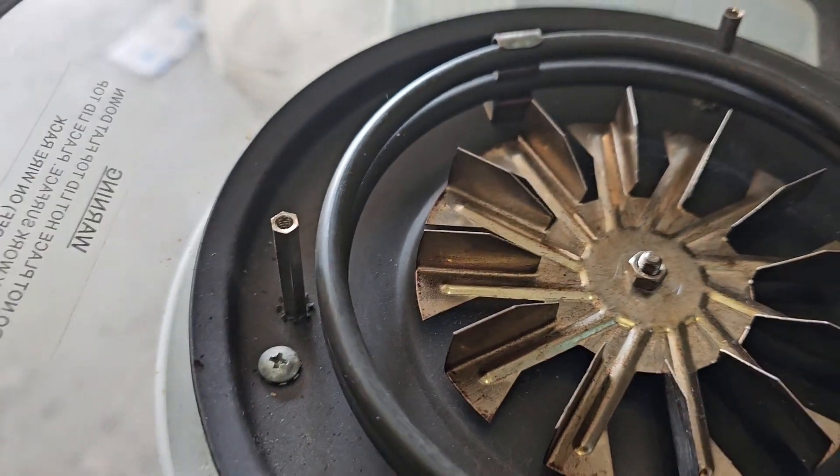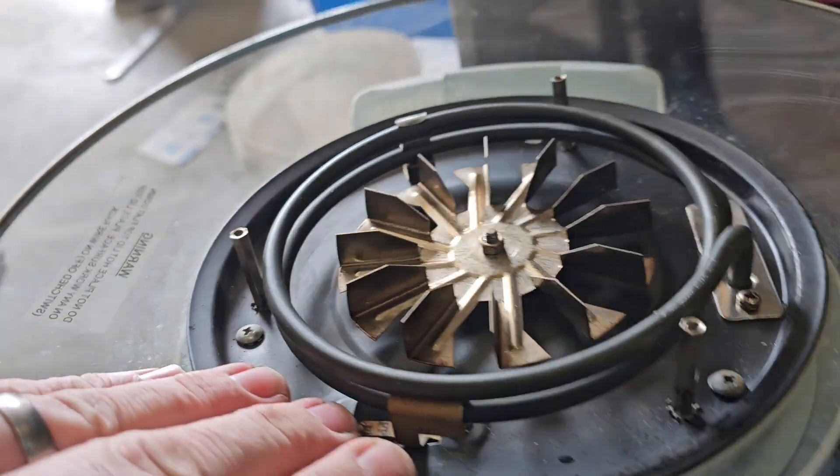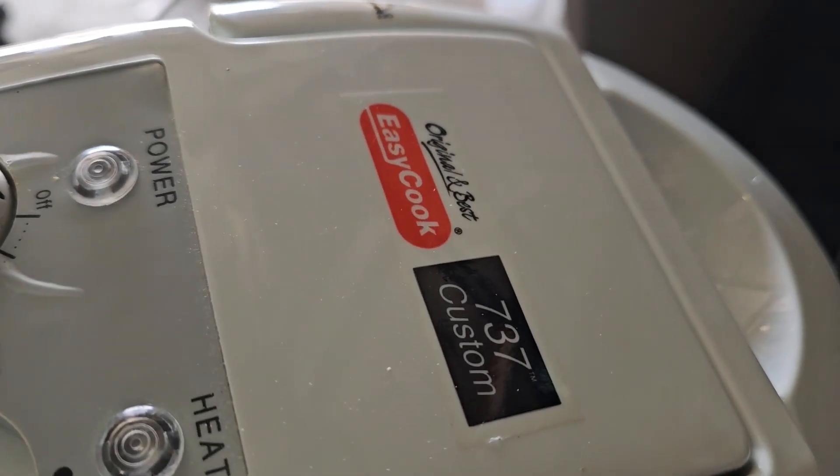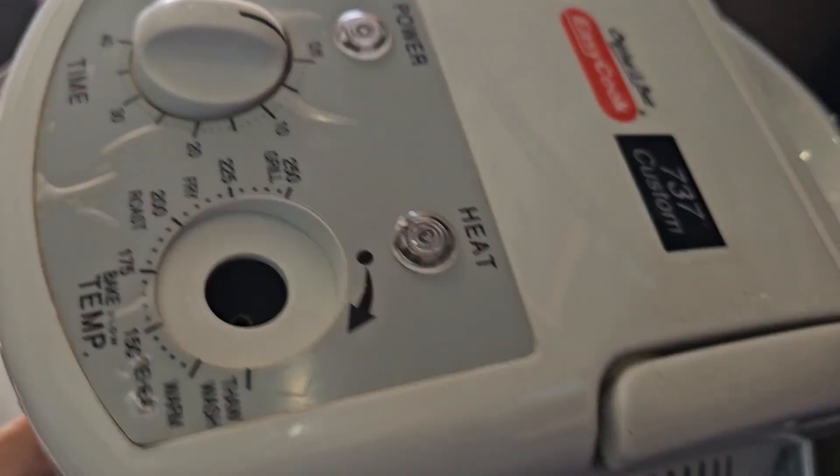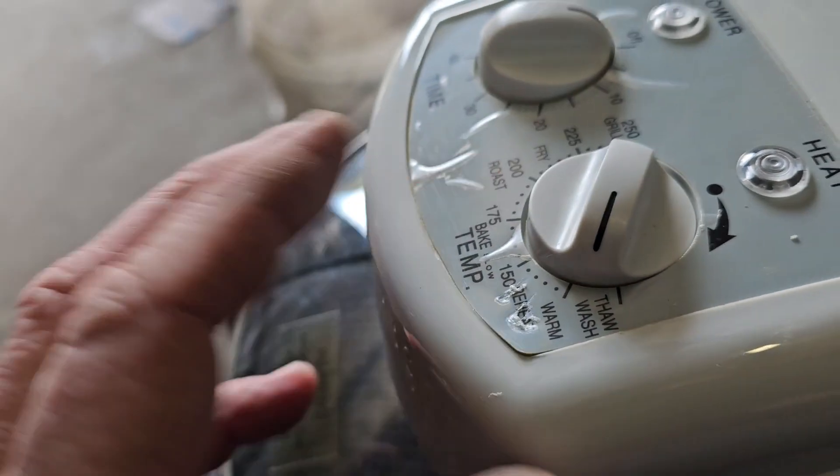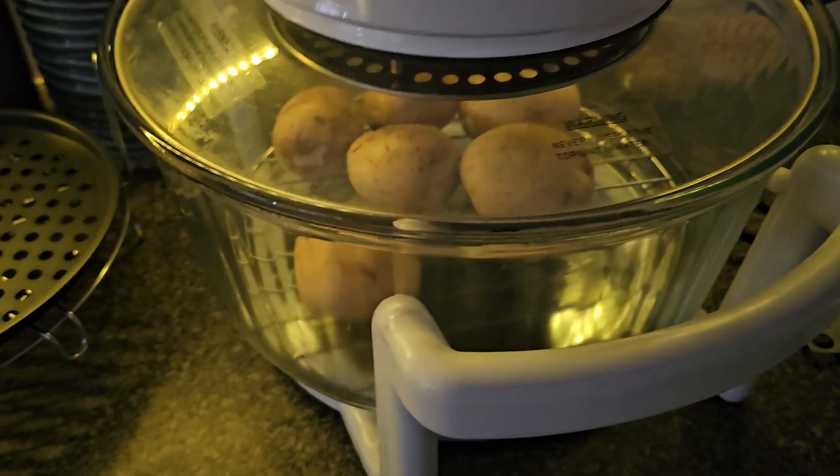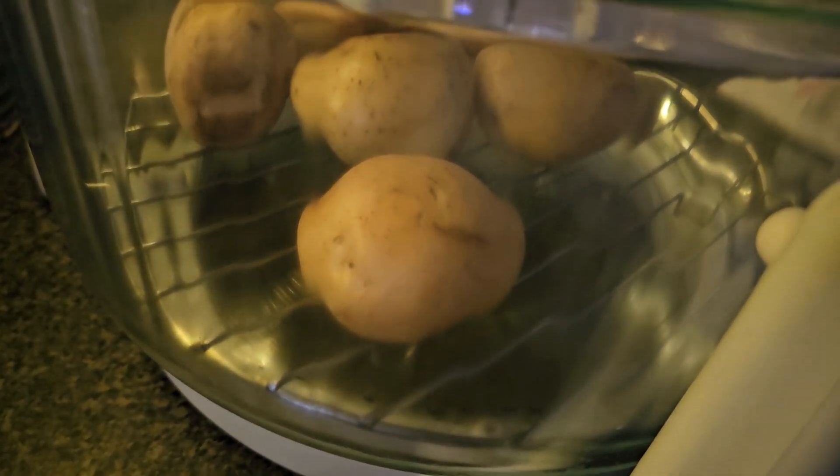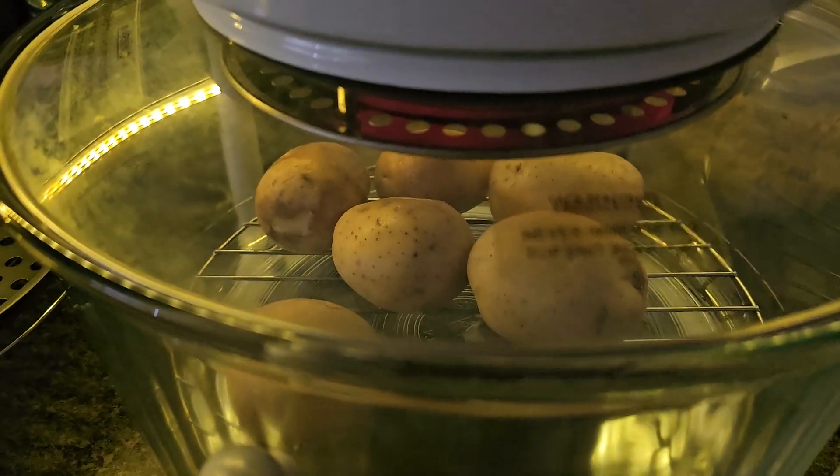Then all you have to do is fit your plate on top. This is the easy cook SO-737, quite a large device compared to your average. This model has got a piece of metal sitting out. You need to position that on that square bit. That's definitely the resistance, around about 45.2 to 45.5 is your resistance you want off one of these cookers.